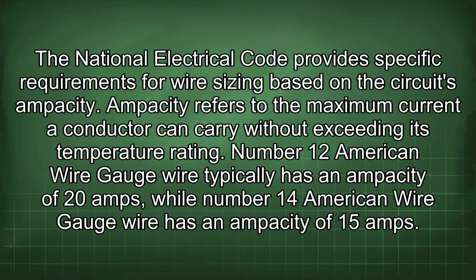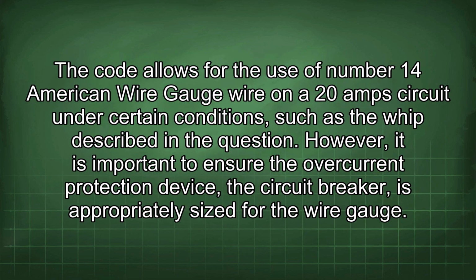The National Electrical Code provides specific requirements for wire sizing based on the circuit's ampacity. Ampacity refers to the maximum current a conductor can carry without exceeding its temperature rating. Number 12 American wire gauge wire typically has an ampacity of 20 amps, while number 14 American wire gauge wire has an ampacity of 15 amps. The code allows for the use of number 14 American wire gauge wire on a 20 amp circuit under certain conditions, such as the whip described in the question.